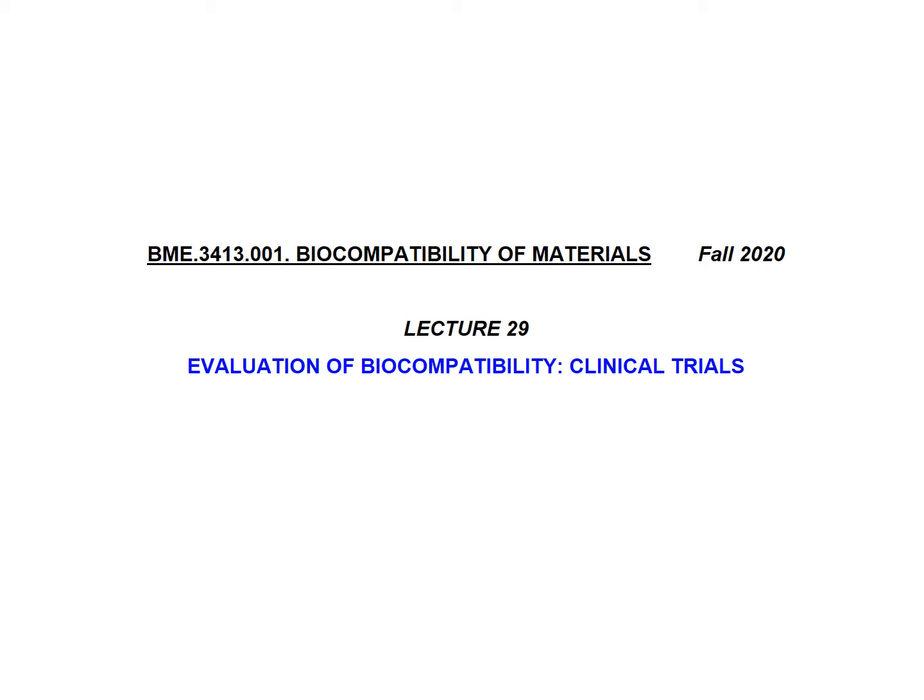The two important prerequisites for clinical trials are the following. First, all other steps of the biocompatibility evaluation process must be completed successfully before clinical trials are even contemplated. The second new and crucial requirement is that clinical trials must be reviewed and must be approved by regulatory agencies such as the Food and Drug Administration in the United States.